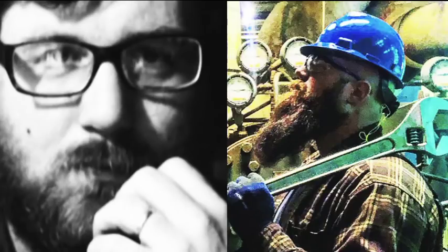So you get that mineral calcium type of deposits that build up on the inside of the pipe, because the condenser loop in a chiller system is an open loop. We pump up to the top of the building to that tower, and we're constantly having to make it up because we're misting that tower water at the top of the tower, and it runs down that plastic fill for that evaporative cooling effect. Well, we constantly lose water. We constantly have to make it up with city water. At least once a year, we want to pull those heads off, drain the machine, and brush those tubes. You ask what size? It depends on the machine. Usually anywhere from 3/8 all the way to 1 inch even.